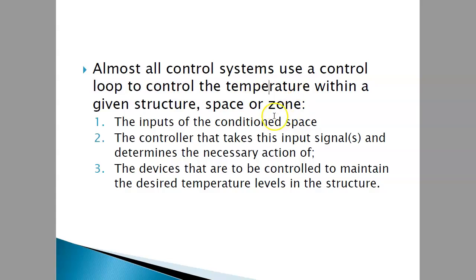So before we could control a space or a room, for example, we need to have the inputs from the conditioned space. We have to know the temperature, perhaps the pressure and the humidity, or the airflow. By having all of these parameters, the signal is taken into the controller, where the controller means a microchip, and it reads the data or input that is sensed by the sensor.